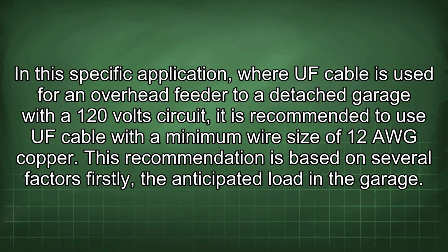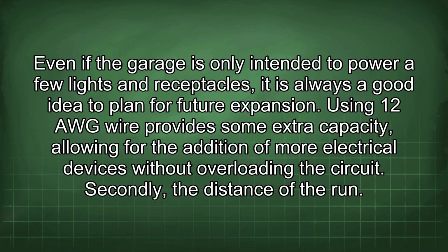In this specific application, where UF cable is used for an overhead feeder to a detached garage with a 120-volt circuit, it is recommended to use UF cable with a minimum wire size of 12 AWG copper. This recommendation is based on several factors. Firstly, the anticipated load in the garage. Even if the garage is only intended to power a few lights and receptacles, it is always a good idea to plan for future expansion. Using 12 AWG wire provides some extra capacity, allowing for the addition of more electrical devices without overloading the circuit.